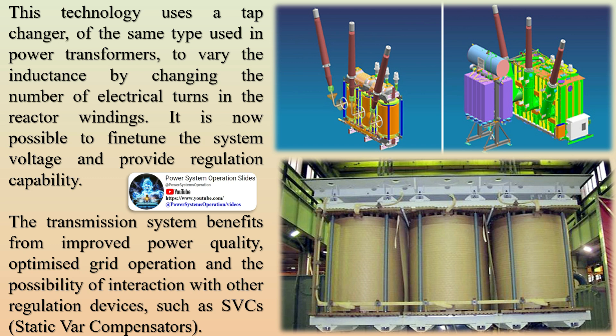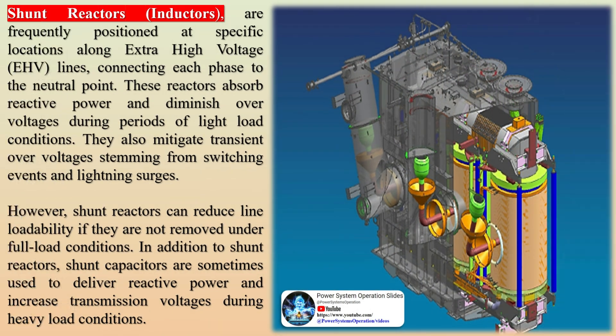The transmission system benefits from improved power quality, optimized grid operation, and the possibility of interaction with other regulation devices such as SVCs (static VAR compensators). Shunt reactor inductors are frequently positioned at specific locations along extra-high-voltage (EHV) lines, connecting each phase to the neutral point.